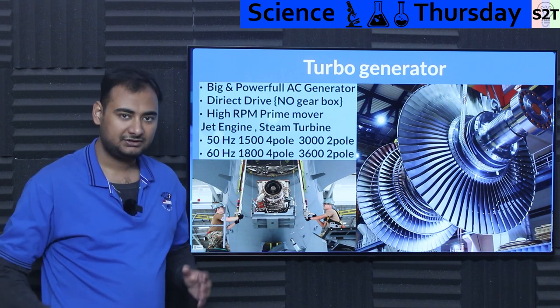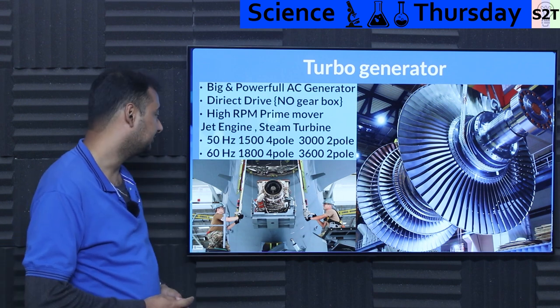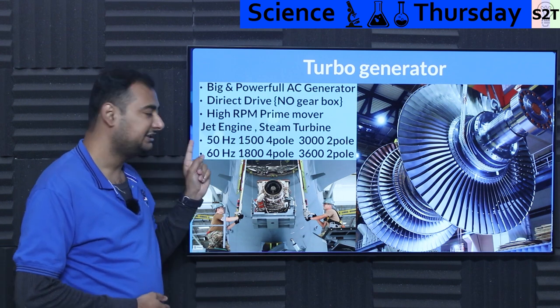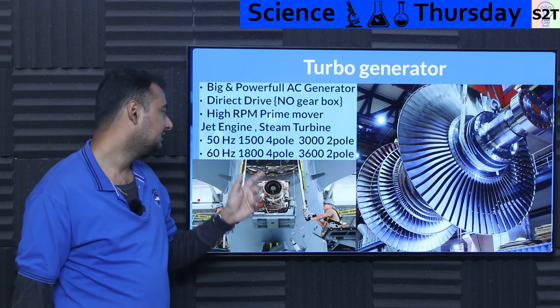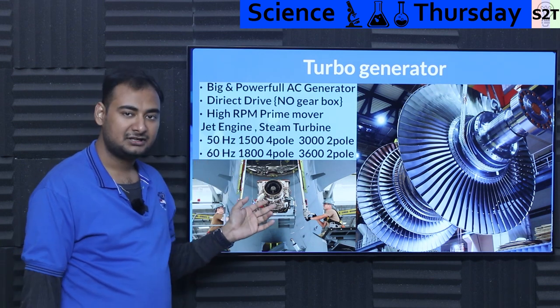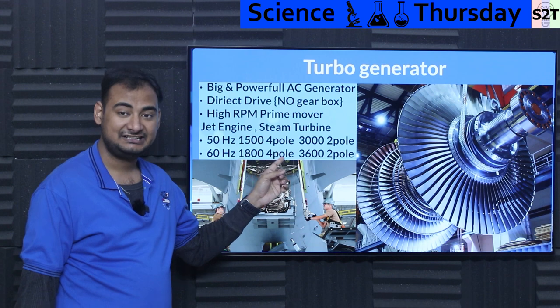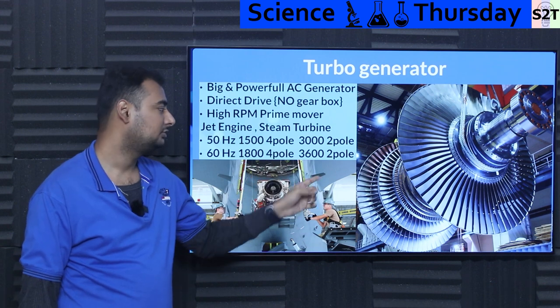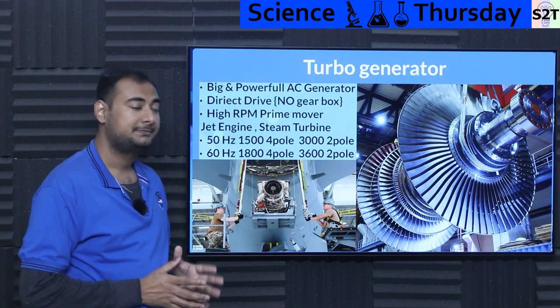To give you context of RPM and frequency: at 50 Hertz, which is the majority of the world, it requires 1500 RPM for a four-pole generator, or 3000 RPM for a two-pole generator.